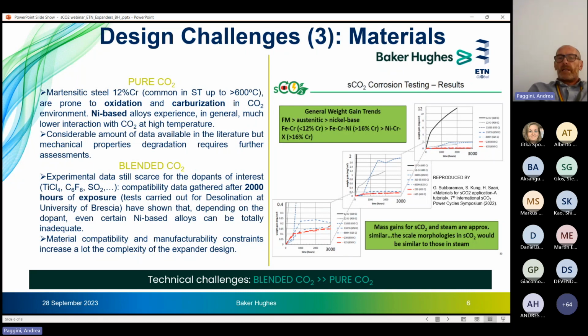behaving extremely well with a certain dopant, experiencing minimal interaction with the fluid after 2000 hours, which is the maximum duration of the exposure tests gathered so far. And the same alloy with another dopant is the least performing, totally inadequate for the application, and you discover it just after a few hundred hours of exposure. So for blended CO2 expanders, materials are a very important challenge.